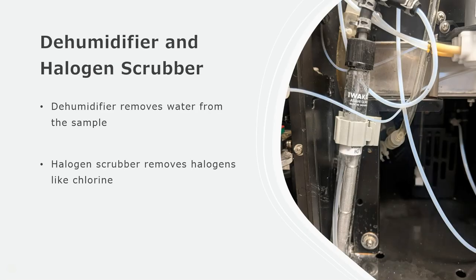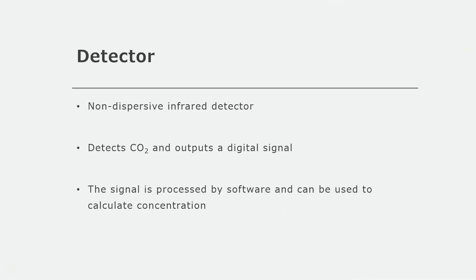After combustion, the sample has water removed from it by a dehumidifier, and then it gets scrubbed in the halogen scrubber to remove things that could damage the detector, like chlorine. The final step in the TOC is the detector, which is a non-dispersive infrared detector. This detects carbon dioxide and outputs a digital signal. This signal gets processed by software which is then plotted to make peaks, and the area under these peaks is proportional to concentration based on your calibration curve.